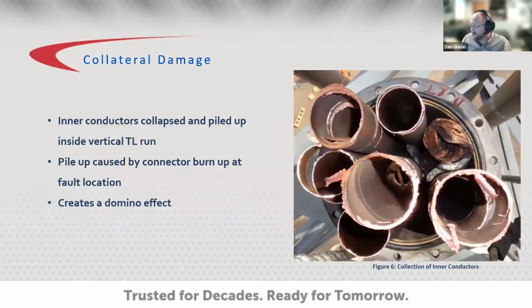Here's another image, and this one's sort of a more powerful image showing the level of destruction that can happen when component degradation goes unnoticed. So the root of this pileup of inner conductors was a failed connector. Similar to the prior image, without a supporting connector component, nothing stabilizes, and the inner conductors cause a domino effect of falling downward due to gravity. And you can see by the rough cuts here, the inspection crew was actually unable to open any of these joints and remove components because they saw copper just blocking their way. So they took a Sawzall and cut across the flange in order to get that out of their way.